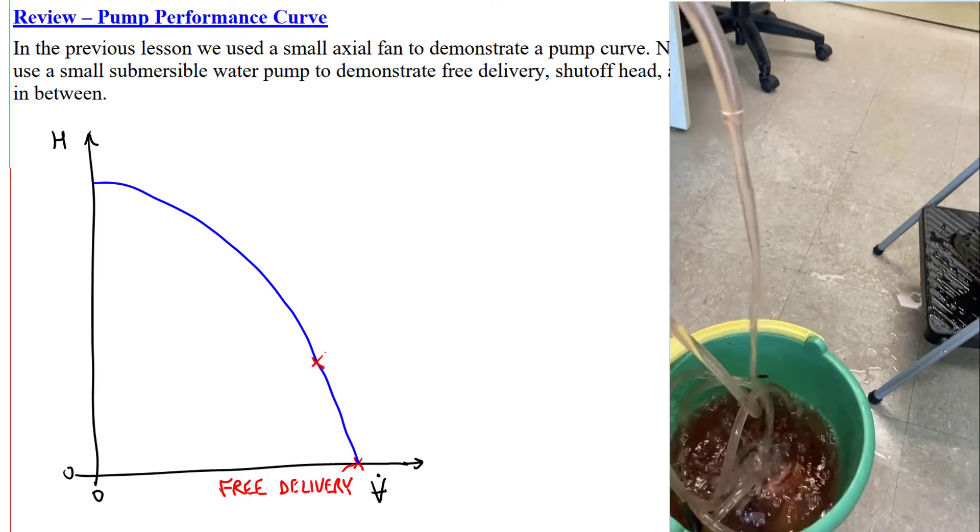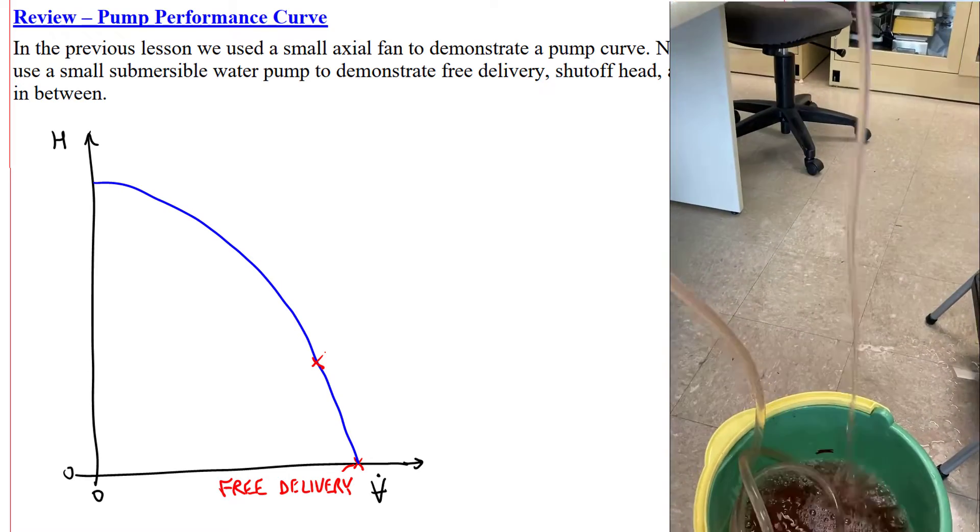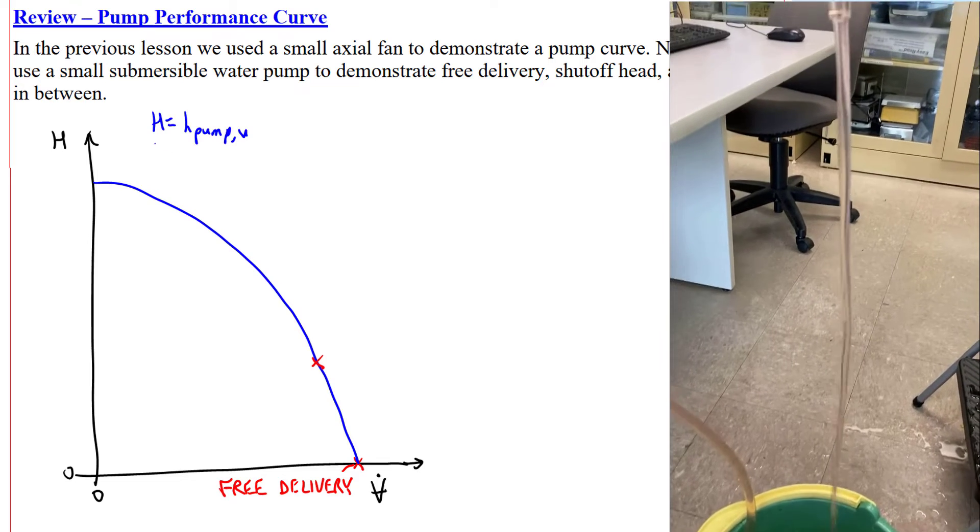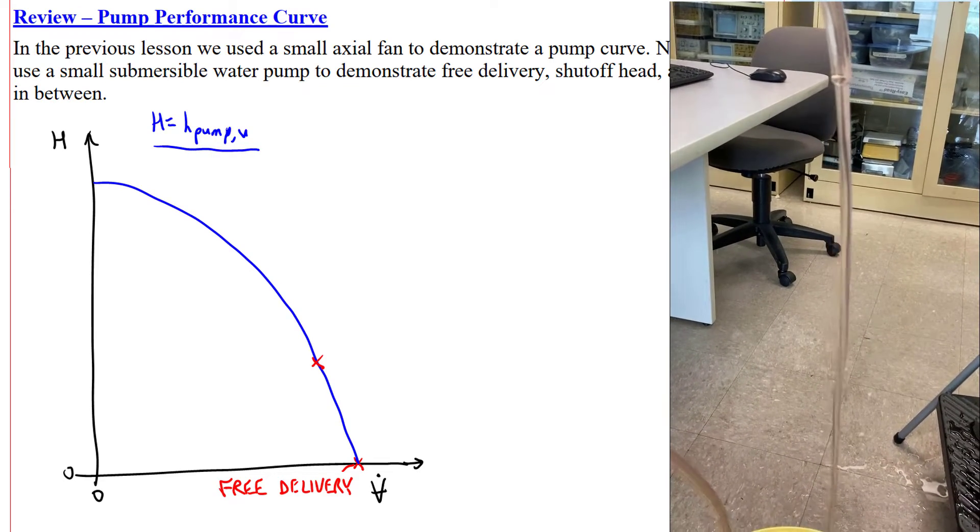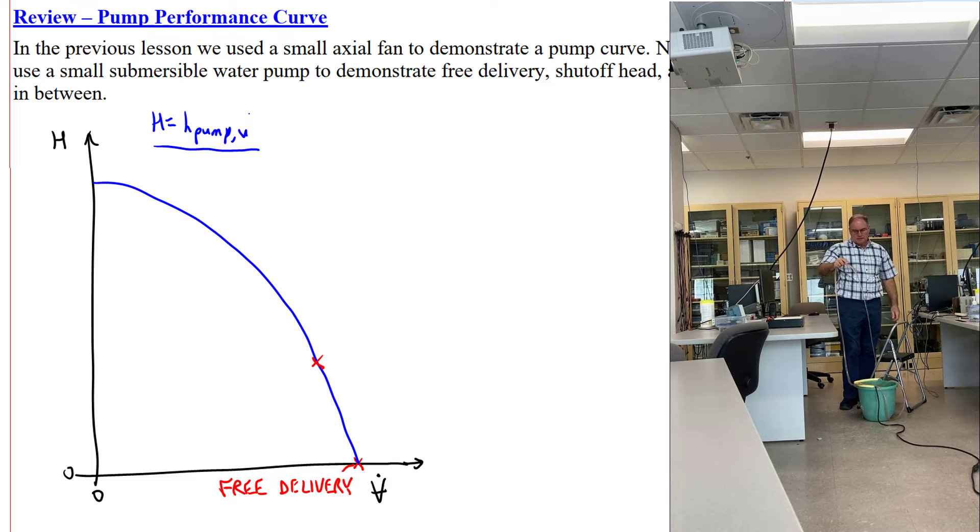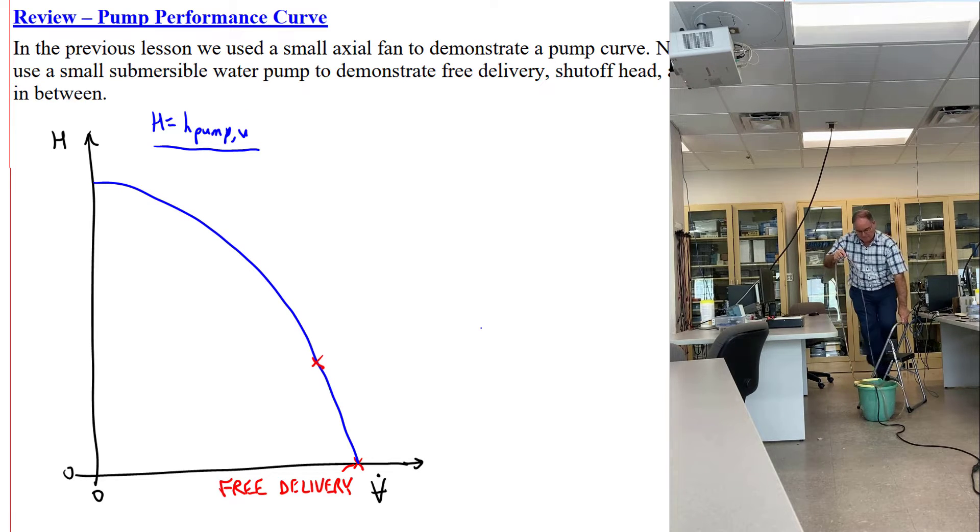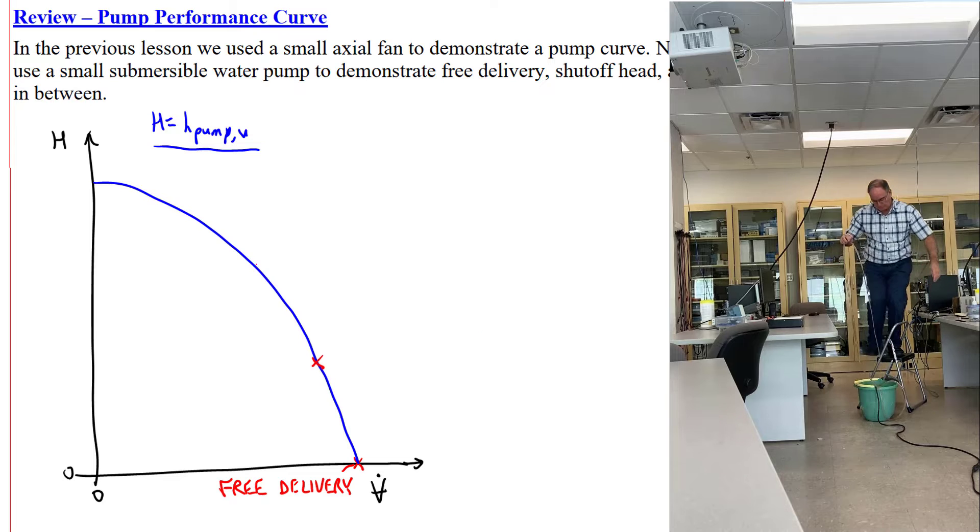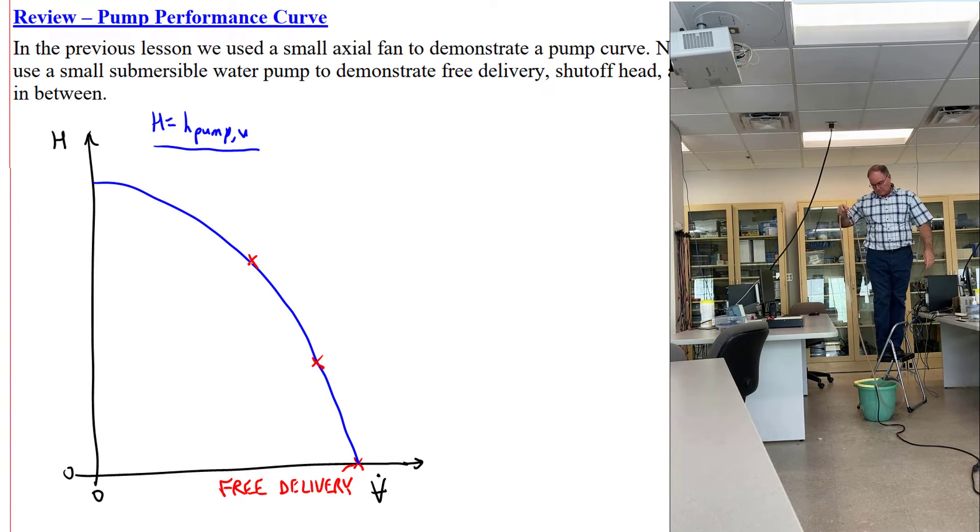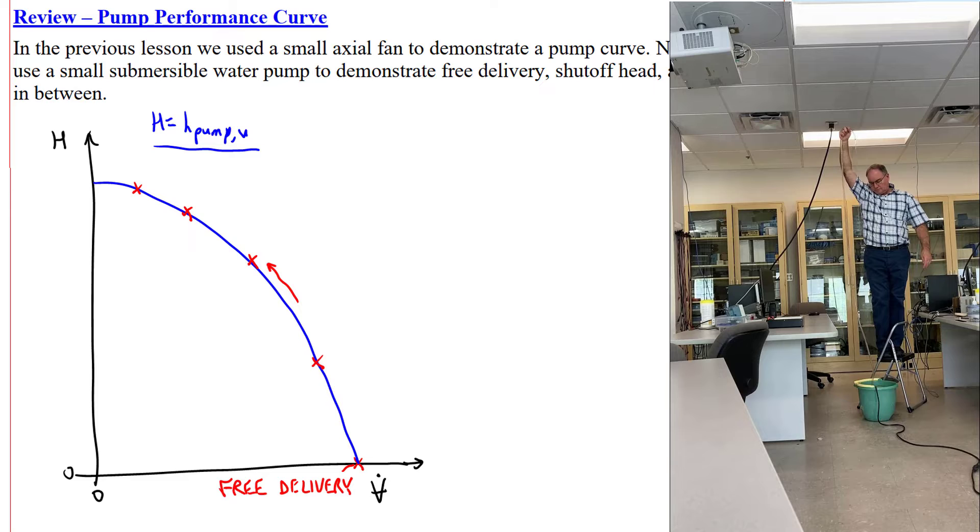As we raise the outlet of the hose, H continues to increase because remember that H is H pump U, the useful head delivered by the pump through the pipe system. This H must overcome irreversible losses and elevation increases. As we continue to raise the outlet, we keep moving along this curve. Now the flow is just a trickle.